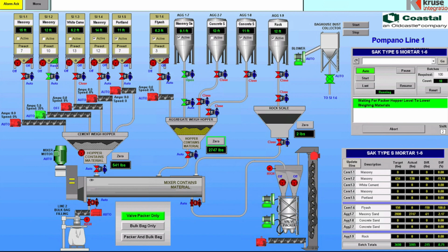In some cases where a valve does not have a screw, where it drops right in, those valves, when it gets near the weight, and this is done in the manager screen, say the total weight of this material that it's asking for is 2808. When it gets to about 2,700 pounds, instead of dropping in real fast, it pauses the valves. So it opens and closes, it jogs the valves, and it does the same with the screws.